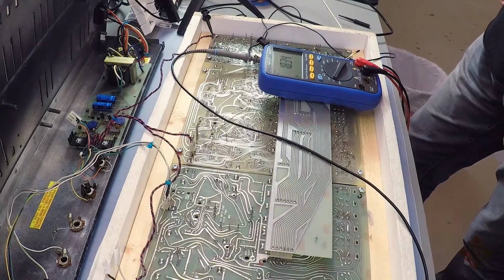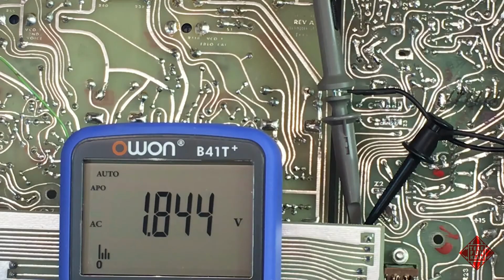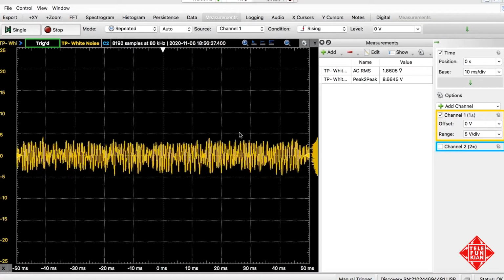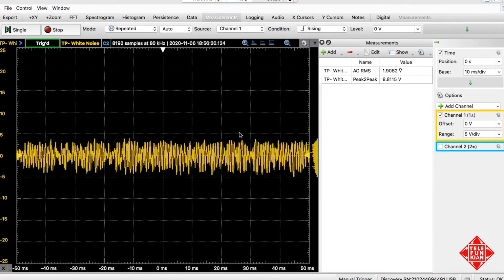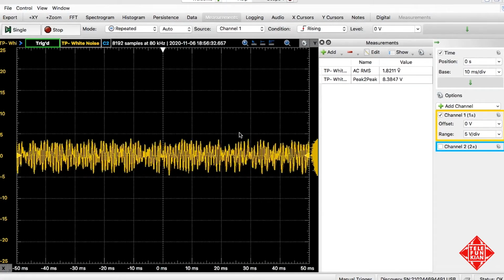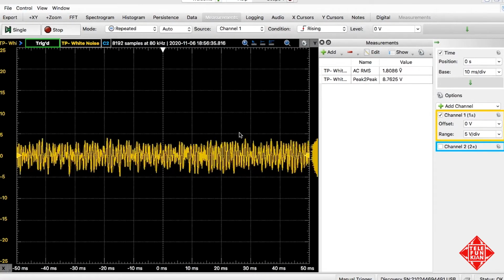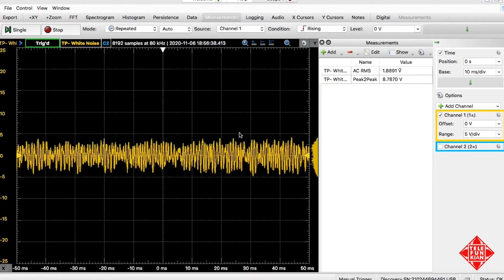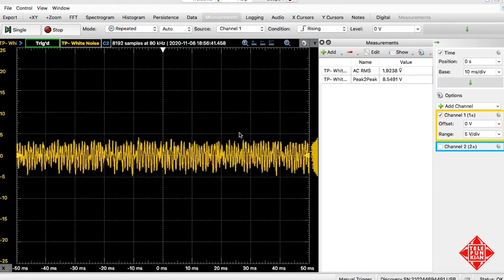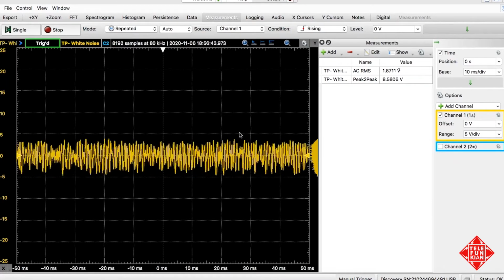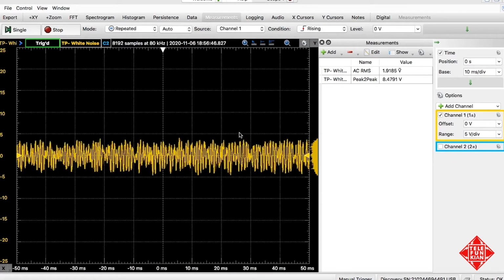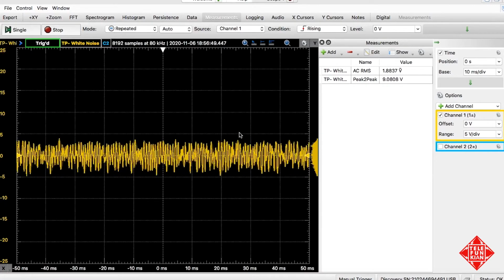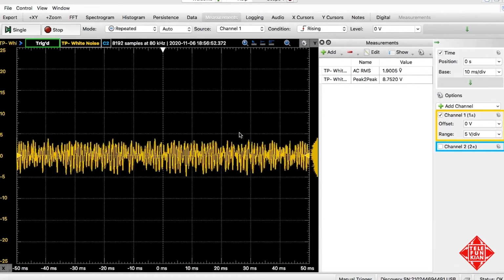So we're currently assessing test point 10 now, which is really the same point on the boards as test point 9, but we've now moved the noise switch from the white noise position to the pink noise position. We see a slight reduction in noise level to about 1.8, 1.9 volts RMS. And if we look at our oscilloscope, indeed we see the character of the signal changing, and it resembles exactly what we would expect looking at the service manual. So again, the white noise and pink noise functions in this instrument appear to be functioning properly.